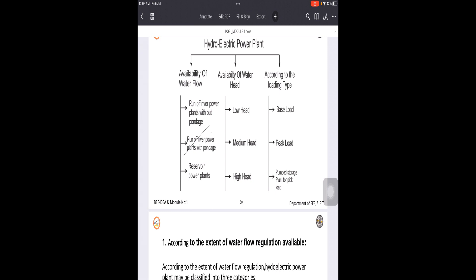The next type is run-of-river power plants with pondage. Here, storage comes into picture. Pondage refers to a small amount of storage at the plant, which makes it possible to generate power whenever water is available and stored. The two limitations we discussed for plants without storage are eliminated here, because even during lean periods the water can be stored and used.